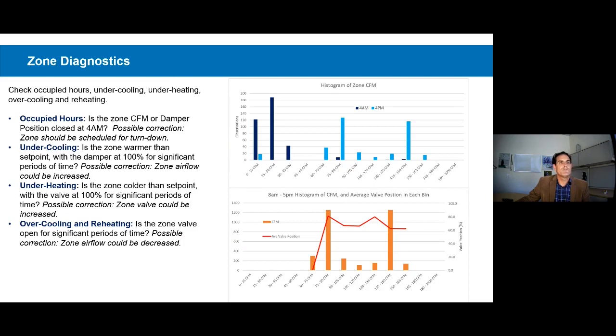So let's get into zone diagnostics, assuming you found some data. What do you do with it for design purposes? There's a list of diagnostics that's down the left side of this slide here. And then these are some diagnostics on zones. The first histogram on this slide is the unoccupied test. I call this the 4 a.m., 4 p.m. tests. So you look at what the zones are doing at 4 o'clock in the morning versus what the zones are doing at 4 o'clock in the afternoon. They should be different. And in this case, their behavior is different, so that's a good thing.